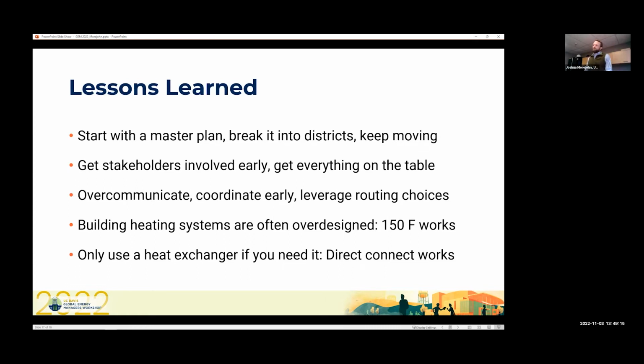What we found is that with some cleaning of those systems, using filtration and strainers ahead of time, we were able to get those heating hot water systems cleaned up and on the same water chemistry as the loop hot water. We ended up not needing heat exchangers really. On our next phases, we're going to look at minimizing the use of those because it really simplifies things in terms of having to size the heat exchanger correctly. It's another piece of equipment that needs maintenance and additional controls and valving.